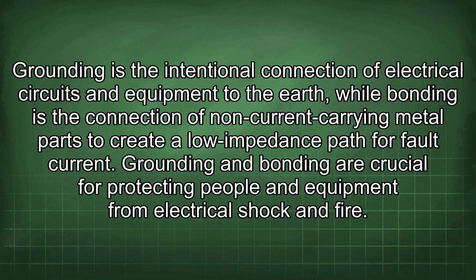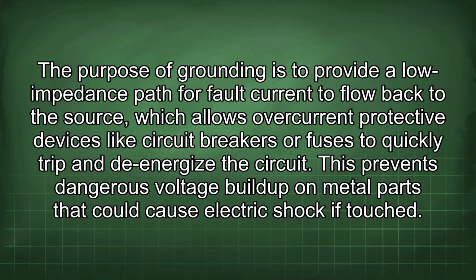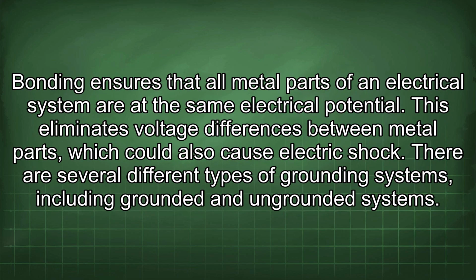Grounding and bonding are crucial for protecting people and equipment from electrical shock and fire. The purpose of grounding is to provide a low impedance path for fault current to flow back to the source, which allows overcurrent protective devices like circuit breakers or fuses to quickly trip and de-energize the circuit. This prevents dangerous voltage buildup on metal parts that could cause electric shock if touched. Bonding ensures that all metal parts of an electrical system are at the same electrical potential. This eliminates voltage differences between metal parts, which could also cause electric shock.